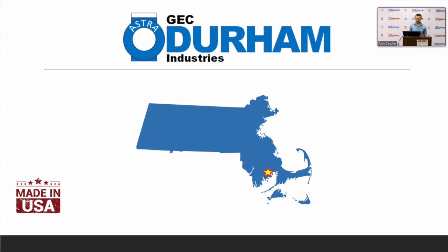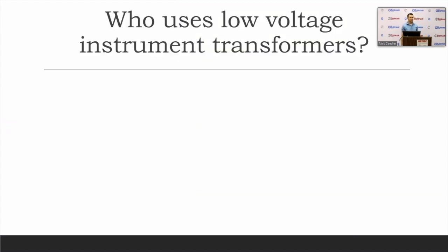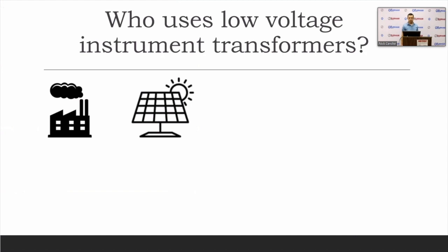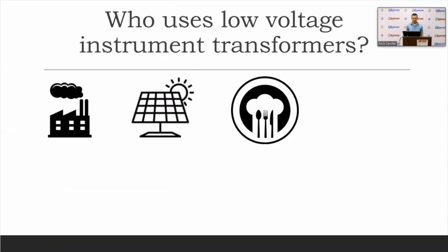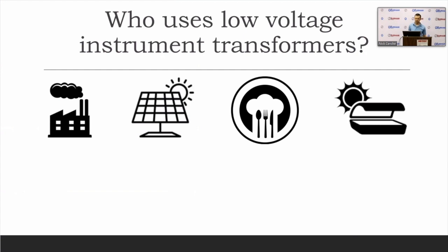Let's take a look at who uses low voltage instrument transformers. We're going to find these in the industry, uses those a lot. Solar, we see a lot of customers reaching out for solar. Down on the low end, these instrument transformers, the high accuracy tend to pick up a lot better. So the solar farms and solar installations use a lot of those. Restaurants are going to use these. We have a Chinese restaurant here in town that has a 1600 amp transformer on it, trans socket with instrument transformers in it.